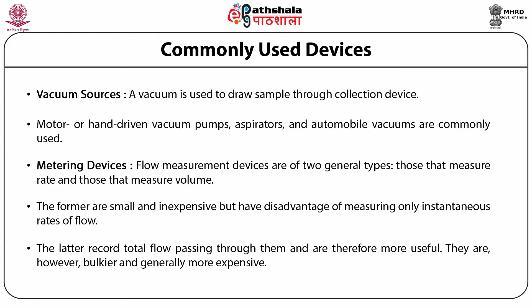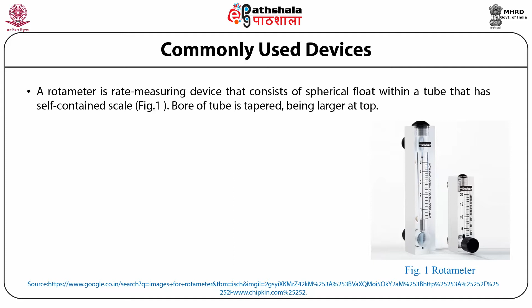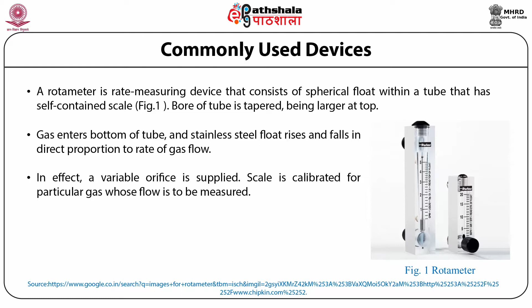A rotameter is a rate measuring device that consists of a spherical float within a tube that has a self-contained scale. The bore of the tube is tapered, being larger at the top, and the gas enters the bottom of the tube, and the stainless steel float rises and falls in direct proportion to the rate of gas flow. In effect, a variable orifice is supplied. The scale is calibrated for the particular gas, for example air, whose flow is to be measured.